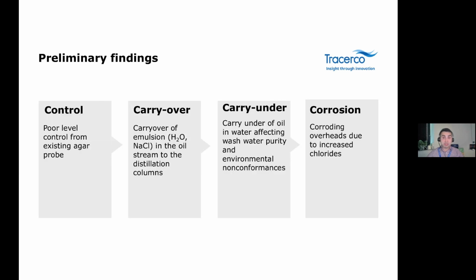Following analysis of the results and in consultation with the client, a Tracerco profiler was chosen to replace all the conventional non-nucleonic instruments in the existing desalter instrumentation with a simple integrated interface, control, and monitoring device, using gamma ray absorption to measure process fluid density and position by the change in radiation intensity.